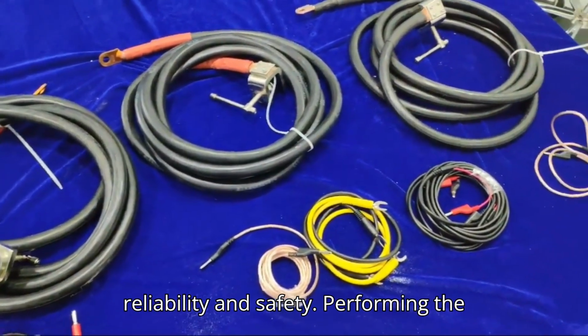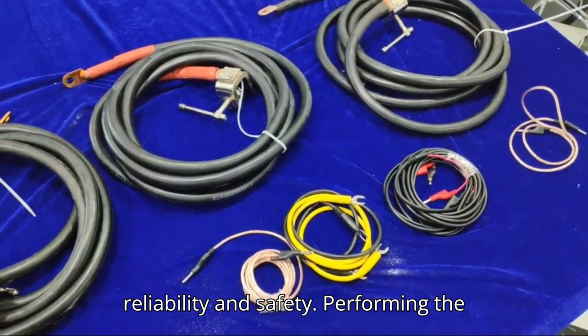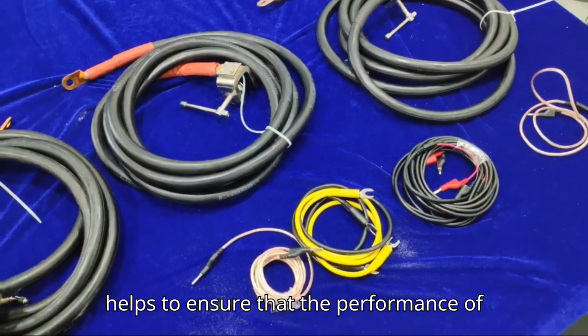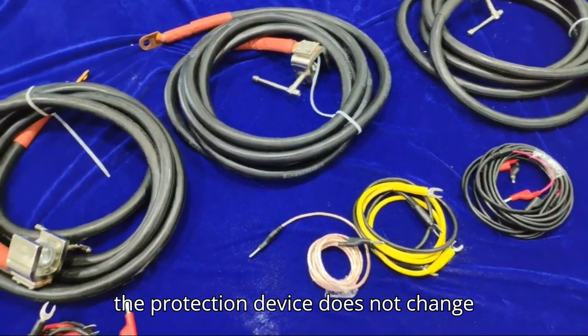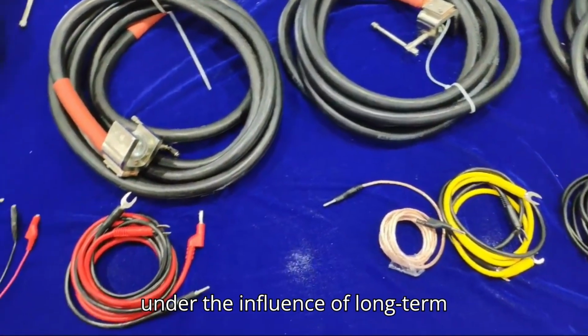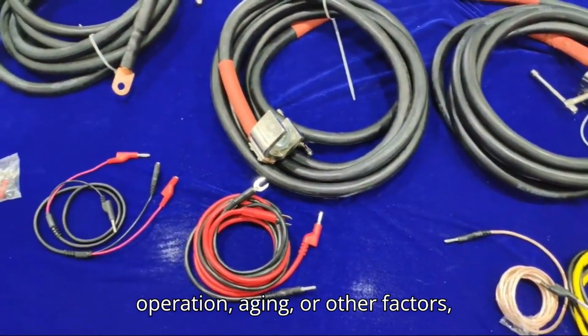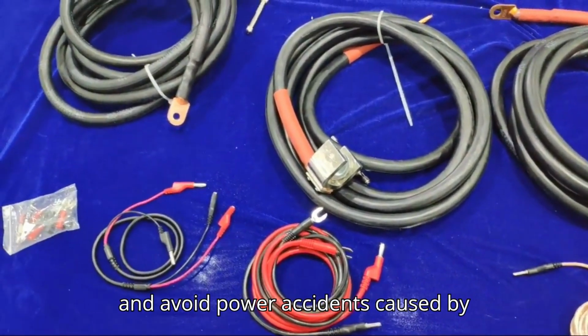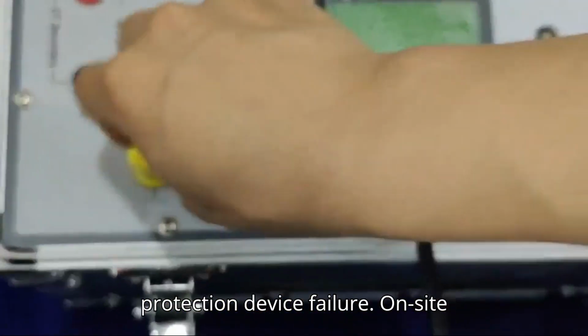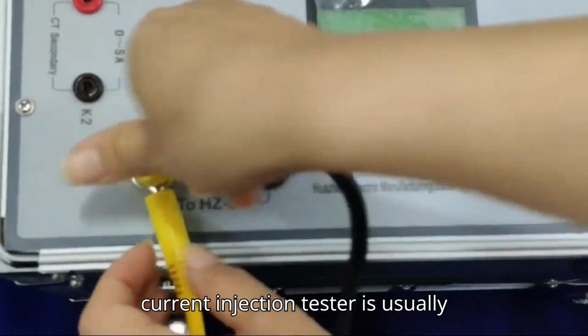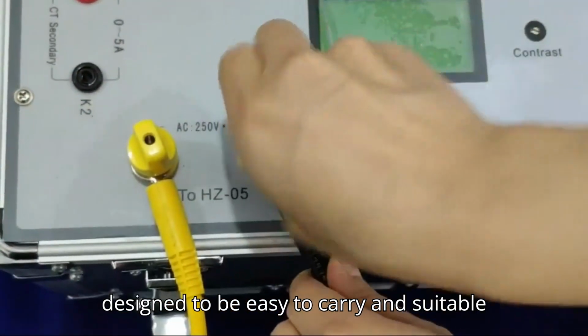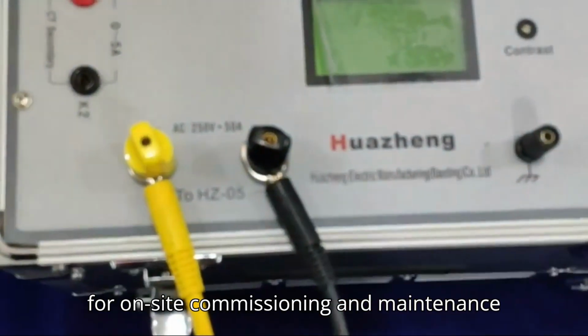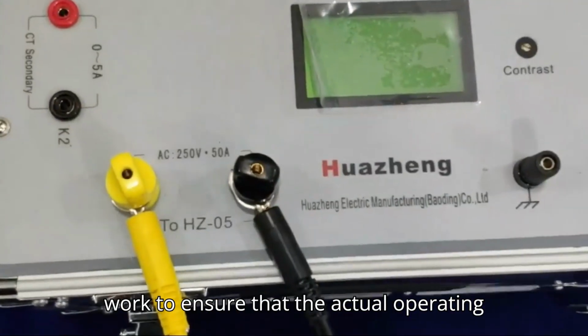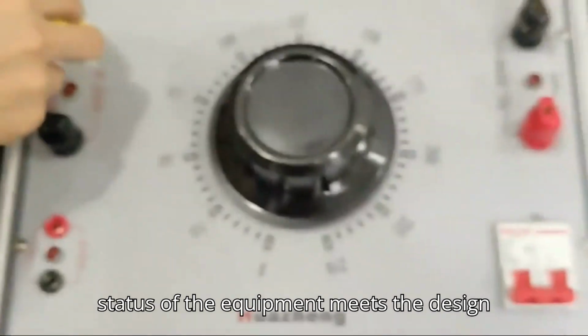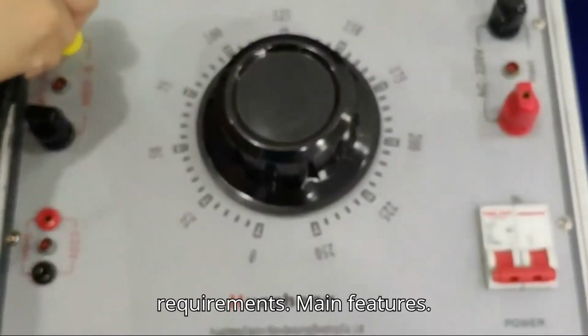Improve system reliability and safety. Performing the main current injection test regularly helps to ensure that the performance of the protection device does not change under the influence of long-term operation, aging, or other factors, and avoid power accidents caused by protection device failure. On-site commissioning and maintenance. The main current injection tester is usually designed to be easy to carry and suitable for on-site commissioning and maintenance work to ensure that the actual operating status of the equipment meets the design requirements.